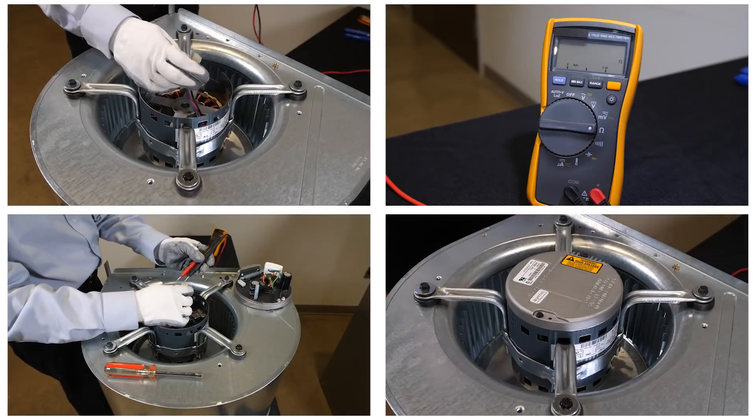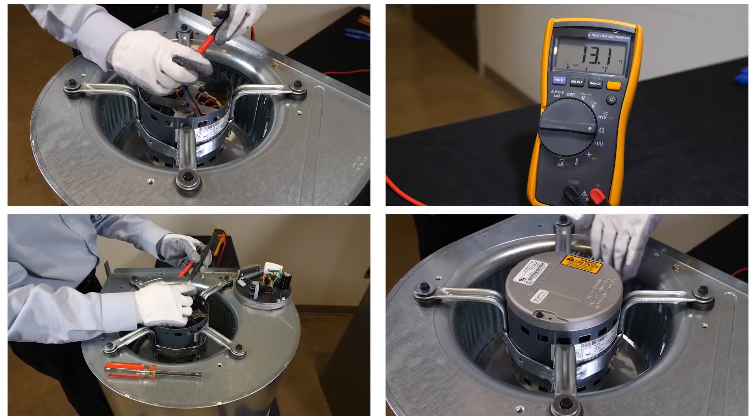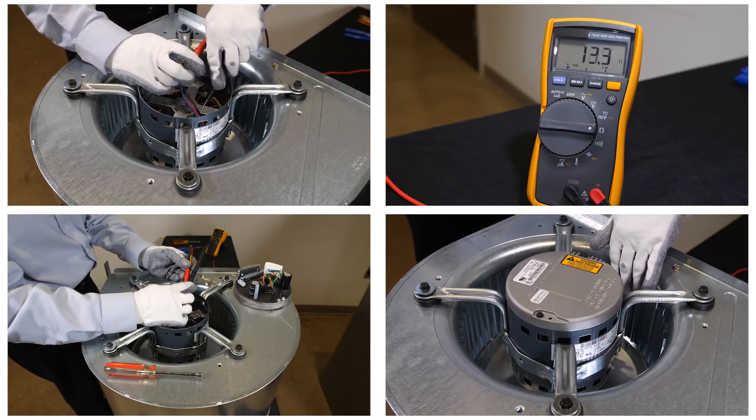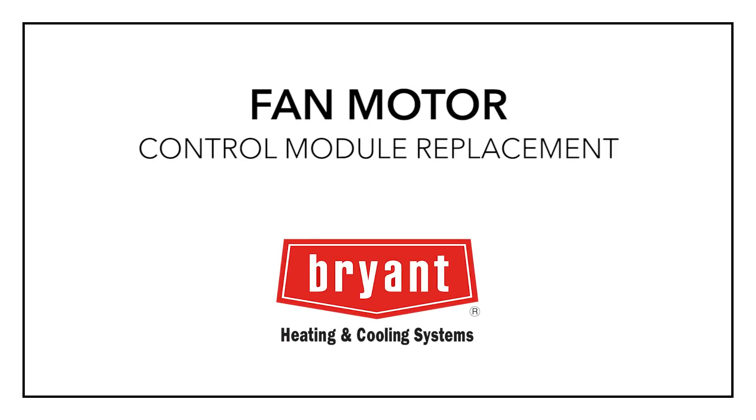If the unit passes all of these tests and the motor still doesn't operate, it's the control module that needs to be replaced, not the entire motor. And it's simple to replace the control module. Like we said earlier, it's just a couple of bolts.